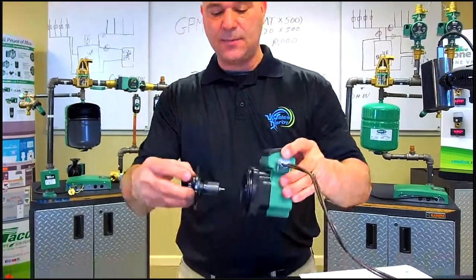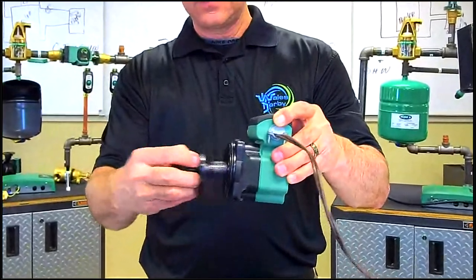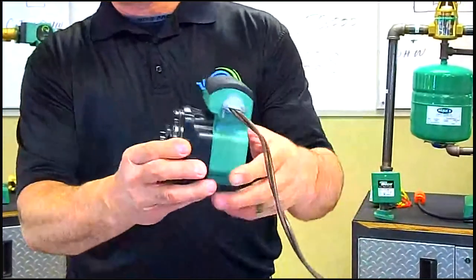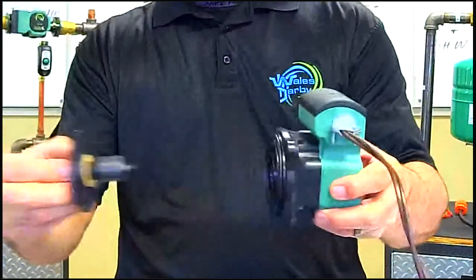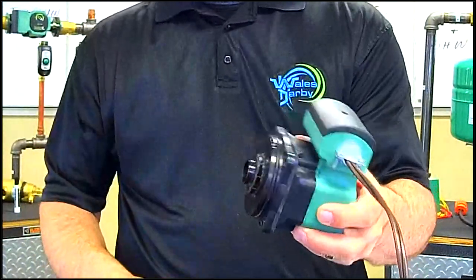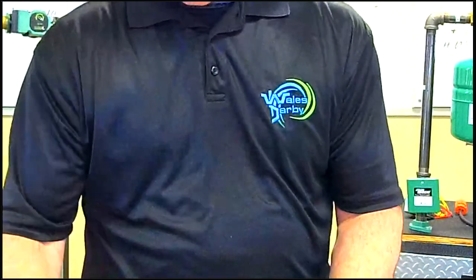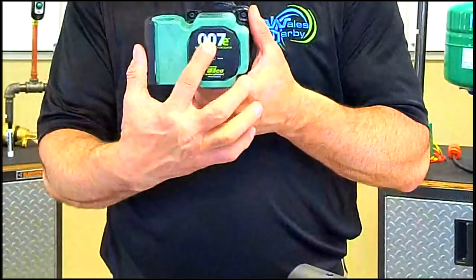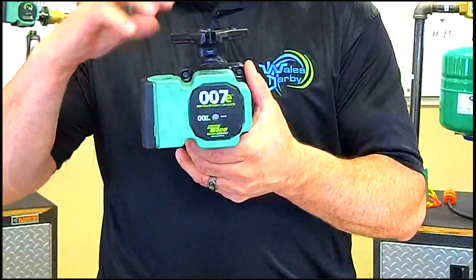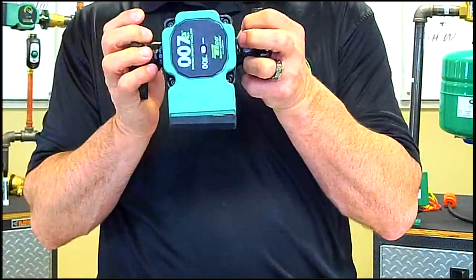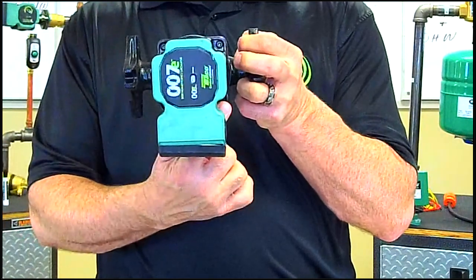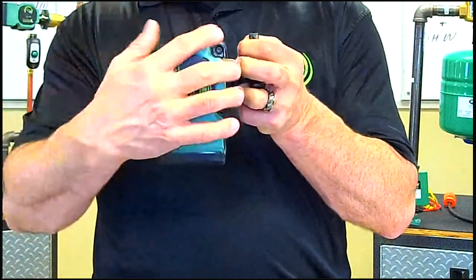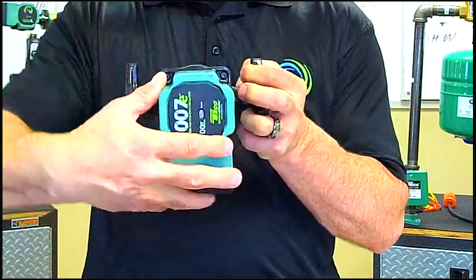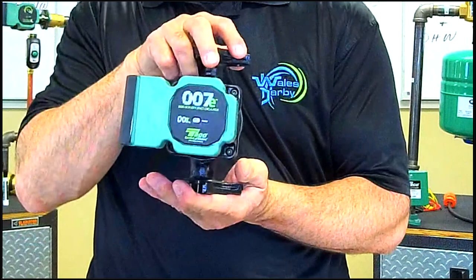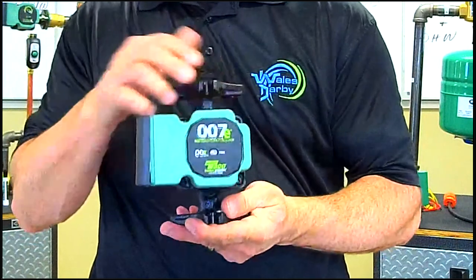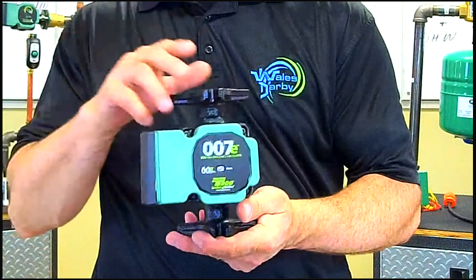So this goes in, you can see it pulls in pretty hard. That's a permanent magnet. If you take a 007 cartridge out, it'll just drop on the floor, but this pulls in pretty good. That's the strength of the magnet. Now, if you ever need to rotate this, we would always like to see the 007 where it's readable. If you're installing this in this orientation, there's four Allen heads. Take those four Allen heads out. Don't pull the motor off the body. Just rotate the motor till it's in this position where you can read it. Put your Allens back in and you're ready to go again.